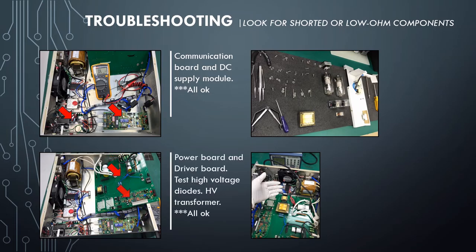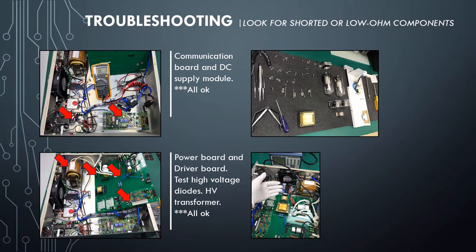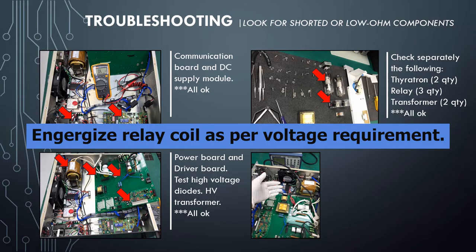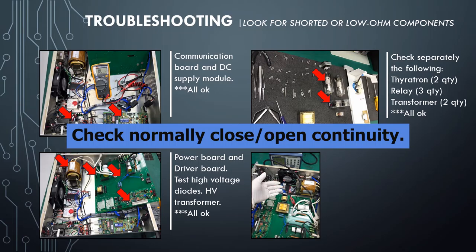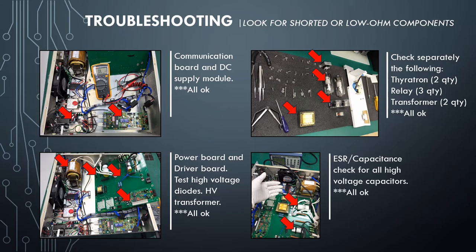Power Board and Driver Board were checked. Testing high-voltage diodes — a multimeter cannot be used to check high-voltage diodes, so I used a different method. Please check the link in the description below. High Voltage Transformer primary and secondary continuity checked — all were OK. Thyratron, relays — energized relay coil as per voltage requirements and checked normally-closed and normally-open continuity. Transformers — checked primary and secondary continuity, all OK. ESR and capacitance check for all high-voltage capacitors — all readings are good.